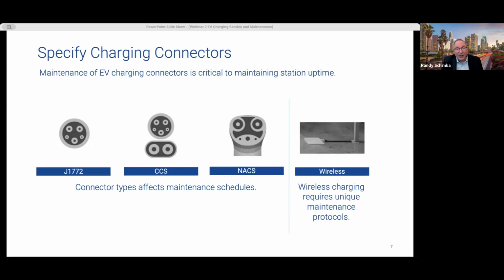Let's talk connector types. We have J1772 connectors for AC level 2 charging and CCS and NACS connectors for DC fast charging. The J1772 connector needs regular inspections to make sure the pins are in good shape and aren't bent, while the CCS and NACS connectors require additional focus on the cables and pins to make sure nothing is discolored or melted due to the higher charging power.